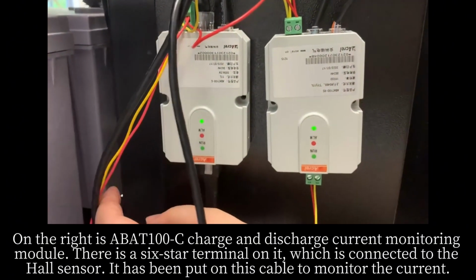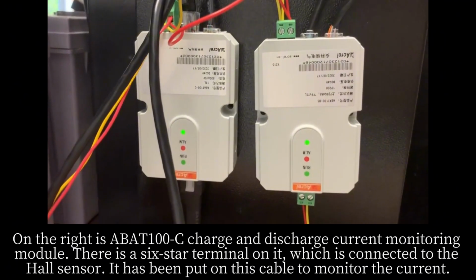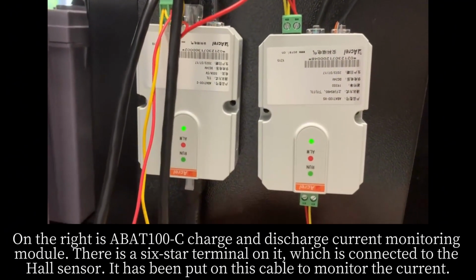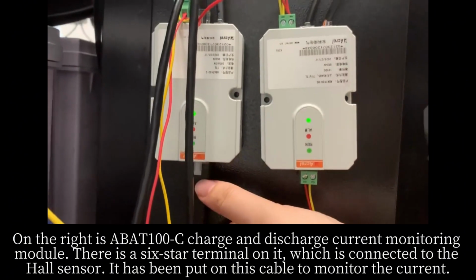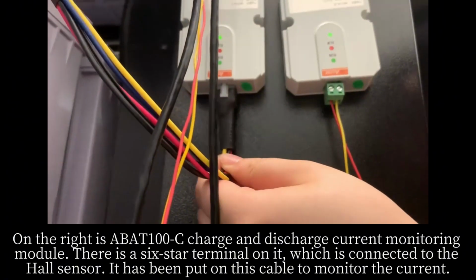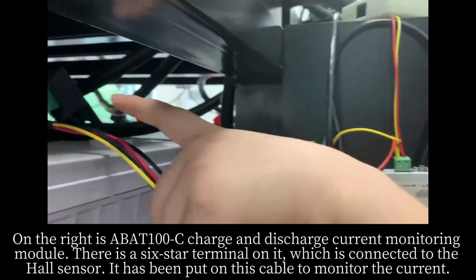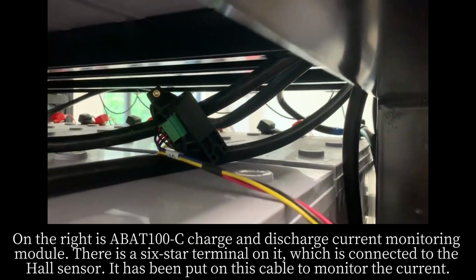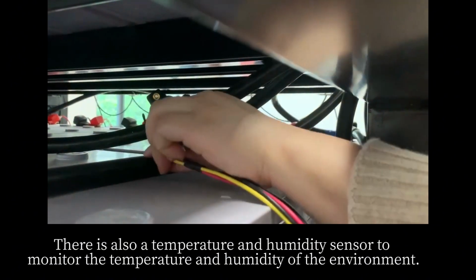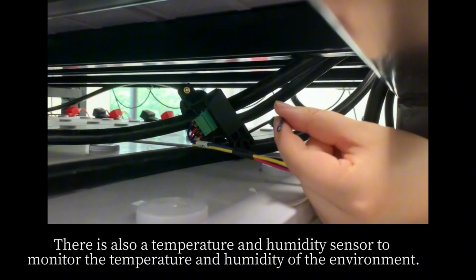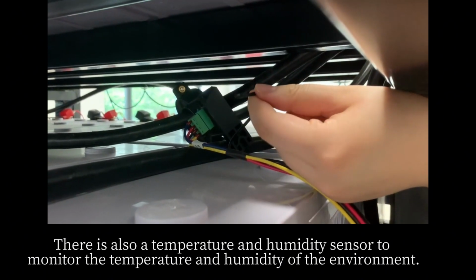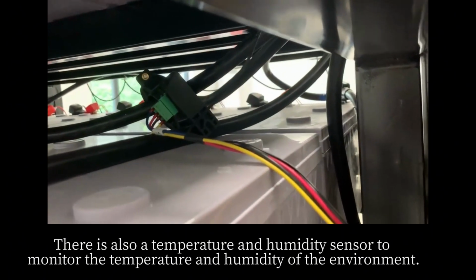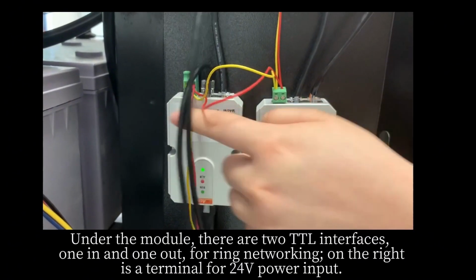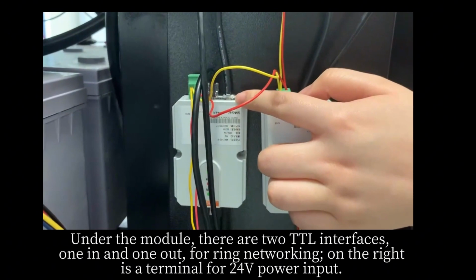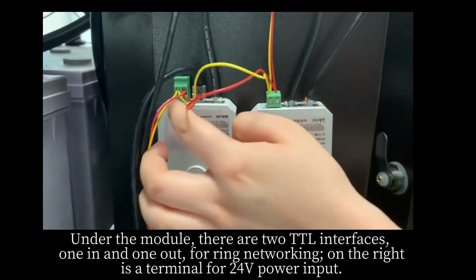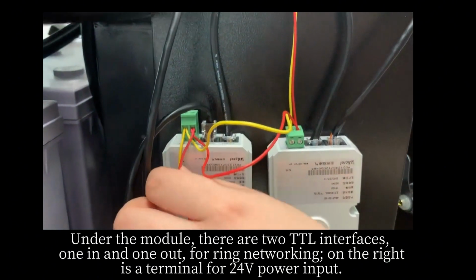On the right is the ABAT100C charge and discharge current monitoring module. There is a 6-star terminal on it, which is connected to the Hall sensor. It has been put on this cable to monitor the current. There is also a temperature and humidity sensor to monitor the temperature and humidity of the environment. Under the module, there are 2 TTL interfaces, 1-in and 1-out, for ring networking. On the right is a terminal for 24-volt power input.